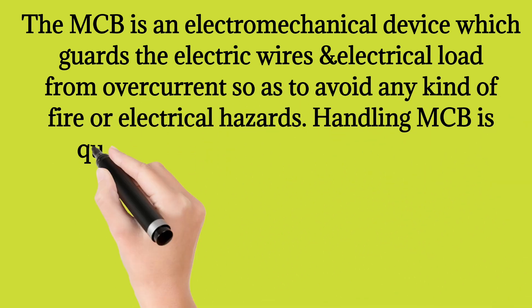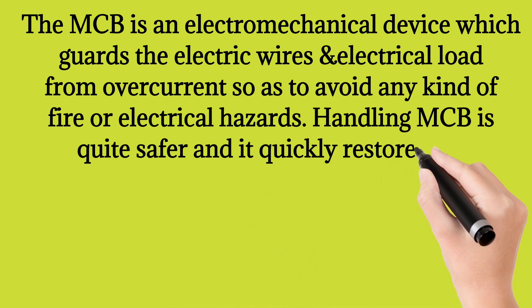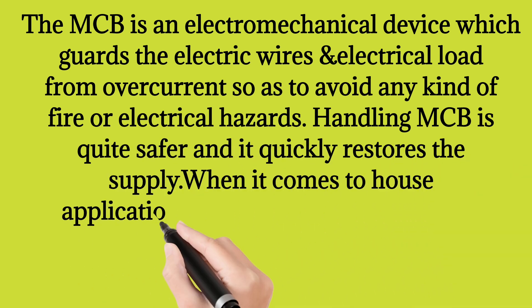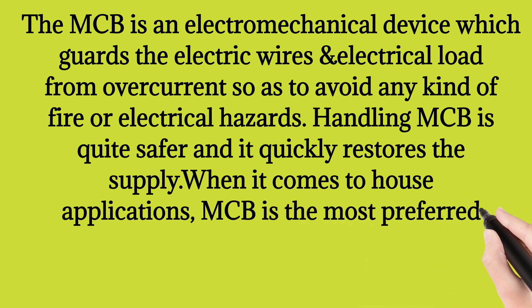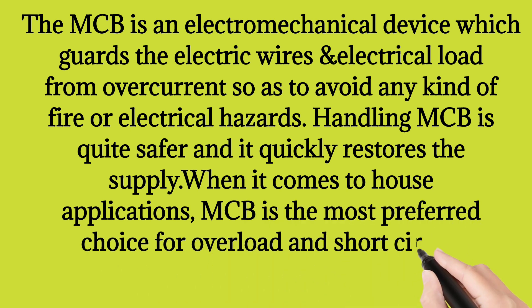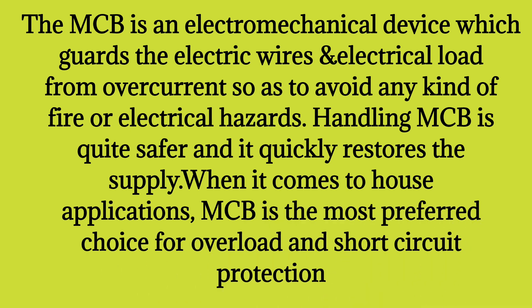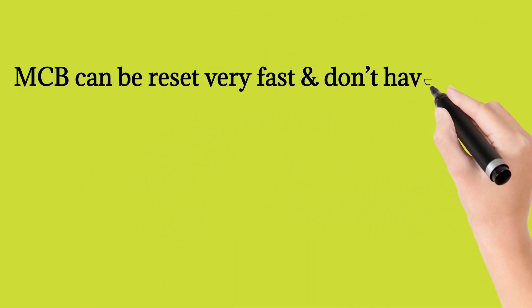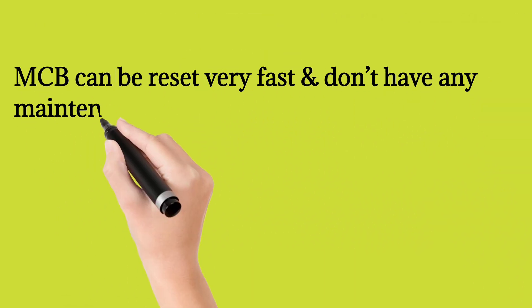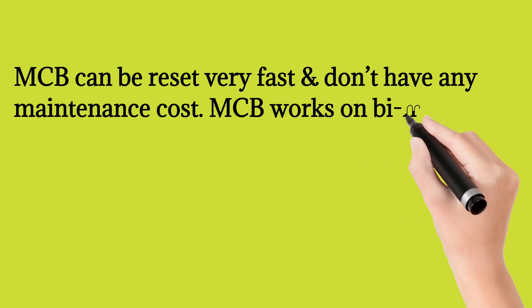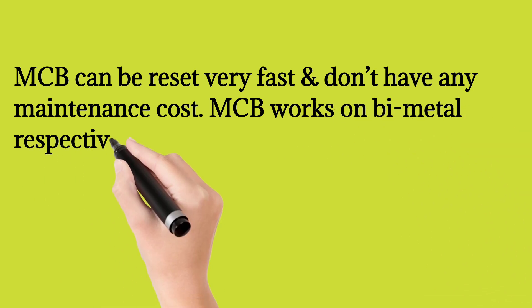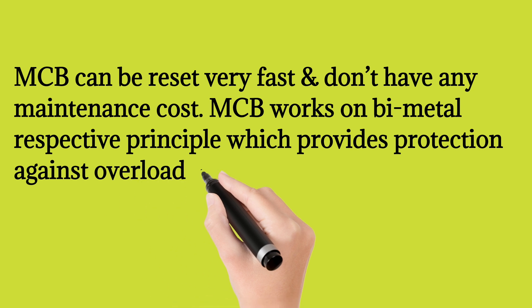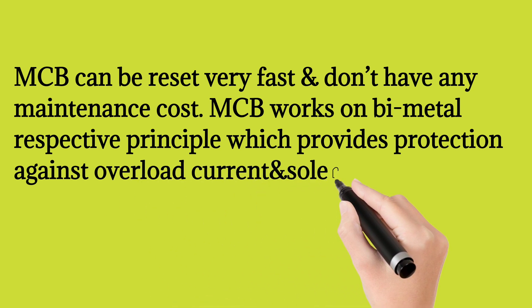Handling MCB is quite safer and it quickly restores the supply. When it comes to house applications, MCB is the most preferred choice for overload and short circuit protection. MCB can be reset very fast and doesn't have any maintenance cost. MCB works on a bimetal strip principle which provides protection against overload current, and a solenoid for short circuit current.